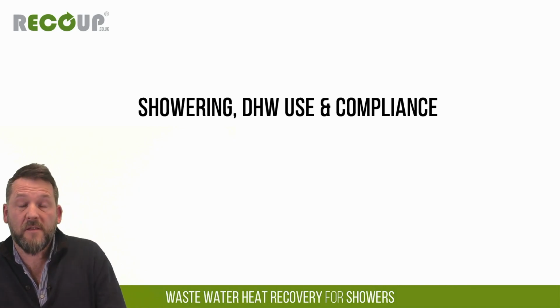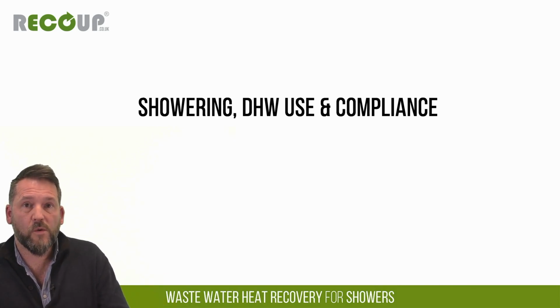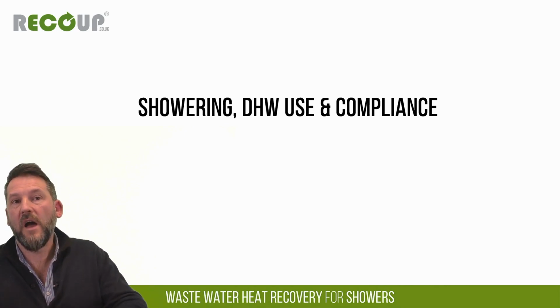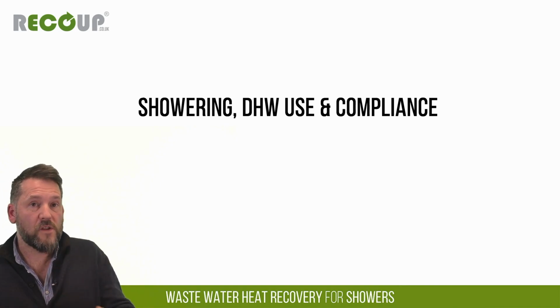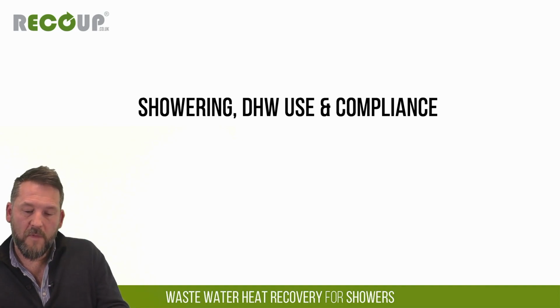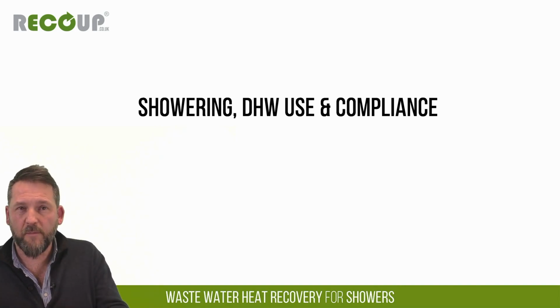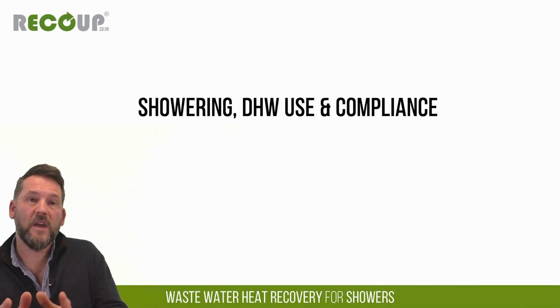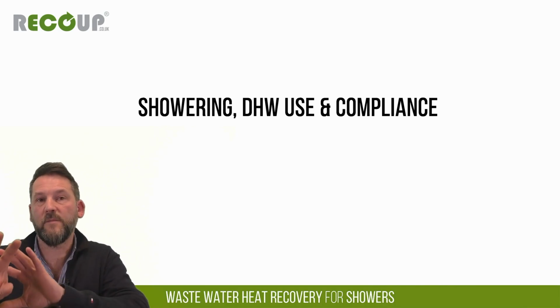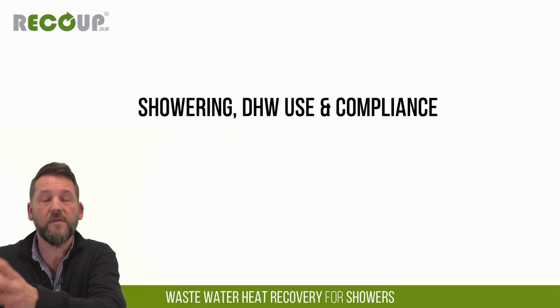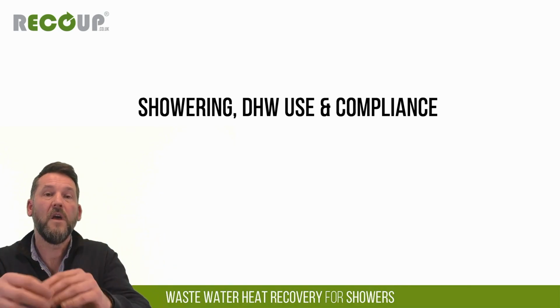Legionella is something that, when you're preheating potable cold water, is always going to come up. All of our products and installation methods are Legionella compliance risk assessed, all deemed lowest possible risk. Installing wastewater heat recovery as per installation instructions shouldn't add any additional Legionella risk to a domestic or non-residential shower scenario. The caveat is that the wastewater heat recovery unit itself, and this applies to the pipe system too, shouldn't be insulated. So if it's boxed in next to an SVP, which is often insulated more for acoustic reasons, the wastewater heat recovery unit itself needs to be left open so it can cool down as quickly as possible.